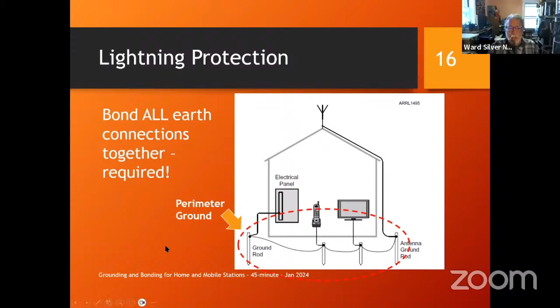So outside, all these ground rods shall be bonded together with a heavy conductor. Number 6 is about the smallest that's allowed; some codes require number 4, number 2, whatever. Get your ground rods out, get a ground rod pounder or hire someone to pound them in for you, and put in a ground rod every 2 times the length of the ground rod—an 8-foot ground rod, then every 16 feet. Outside the house, connect them all together as much as you can. You may not be able to go all the way around the house, but do as much as you can. That's sort of a protective ring, and that's called a perimeter ground.